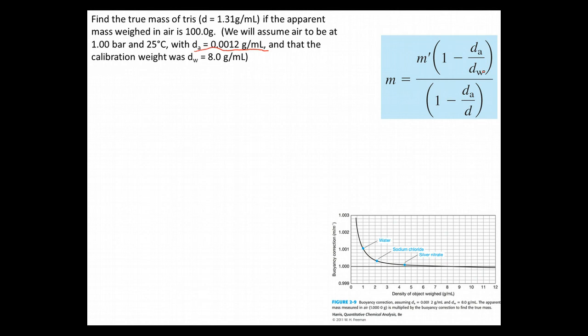You're going to say, well, this weighs 8 grams. You're going to hit the correct button on your scale. You're going to input that it's 8 grams. The scale says, oh, okay, cool. The signal that I'm seeing right now means 8 grams. Wonderful. I am now calibrated.